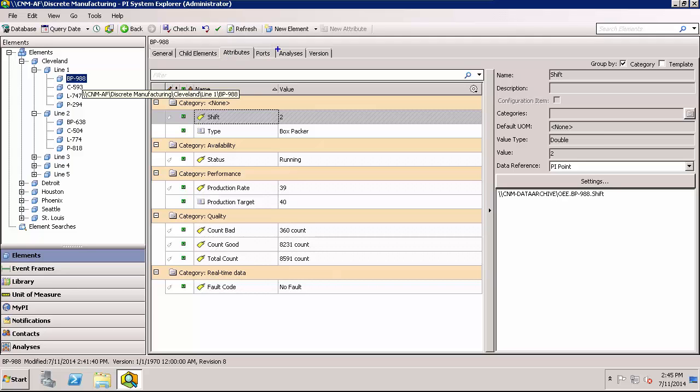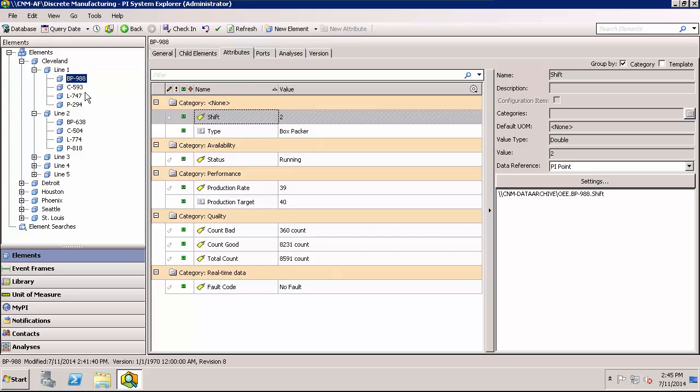Expressions are configured for a given element using the analyses tab. If you don't see this analyses tab in PI System Explorer, you probably aren't using the latest version of the PI Server which includes AF 2.6 or you don't have the latest version of the client tool. But there are a lot of pieces of equipment in this AF database. There's just these four for this line but there's multiple lines and multiple sites. And I don't want to set up that calculation for each individual piece of equipment. Fortunately, these equipment elements were built off of a template.